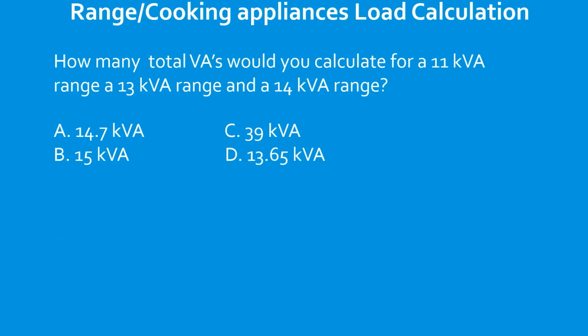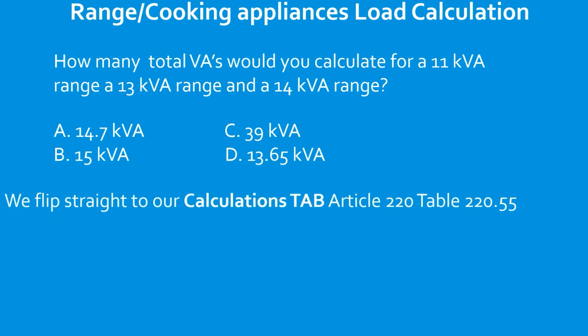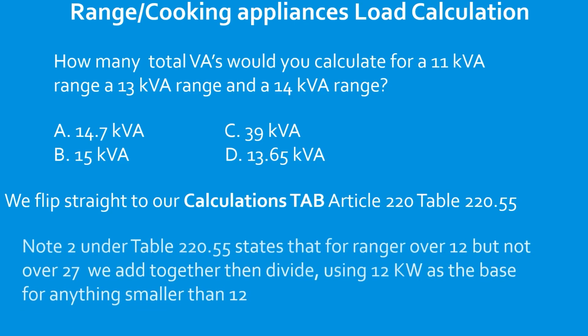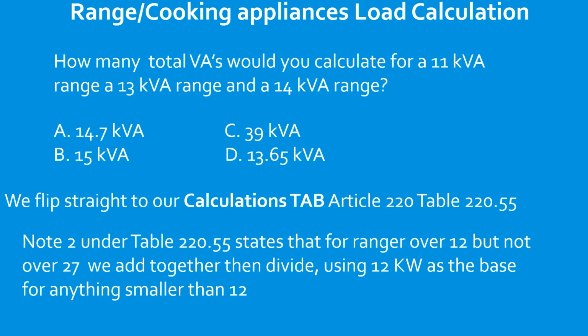How many total VAs would you calculate for an 11 kVA range, a 13 kVA range, and a 14 kVA range? All right, so we're going to use our calculations tab, head to Article 220, Table 220.55. Well, this is an unusual situation, so we know that we're going to be using one of the notes. And in this case, we're going to be using note 2. So this says for ranges that are over 12, but not over 27, we're going to use note 2. And we're going to total all of those ranges' kVAs, then we're going to divide by the number of ranges we have, and we're going to treat that as a normal setup for increasing the column C value.